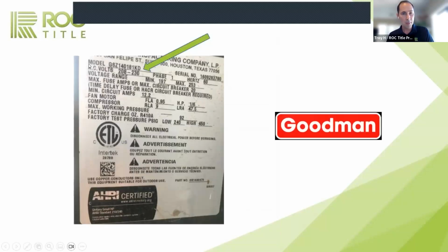Here's another example. What type of a system is it? So we would go to the model number, and that's what's going to show it. First of all, we know the 14 stands for 14 SEER. The 18 stands for 1.5 tons. We divide that by 12.